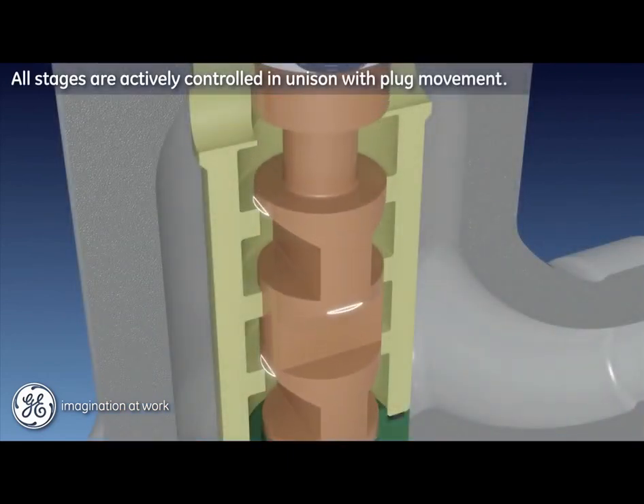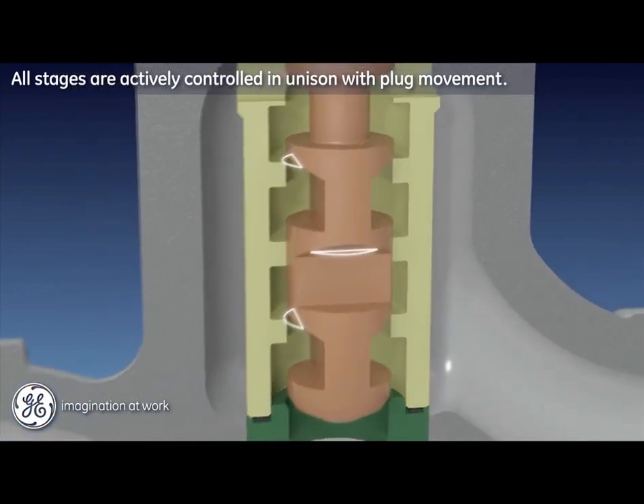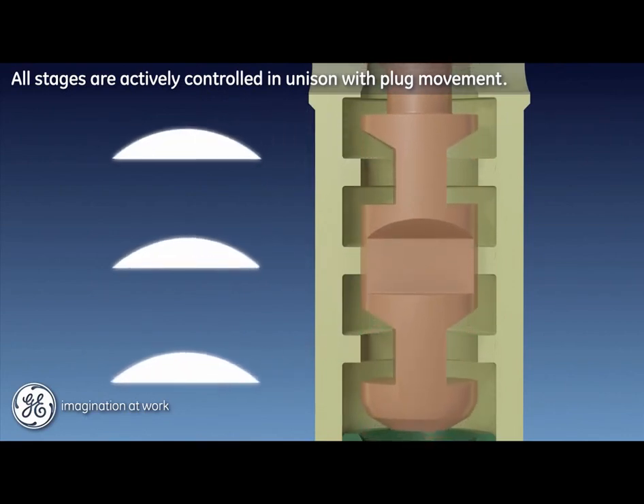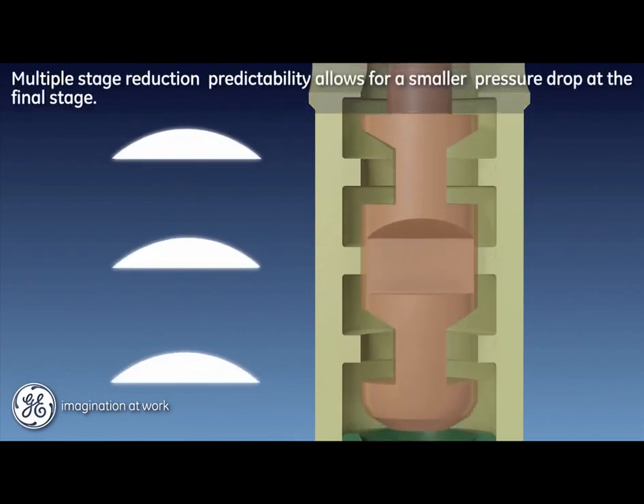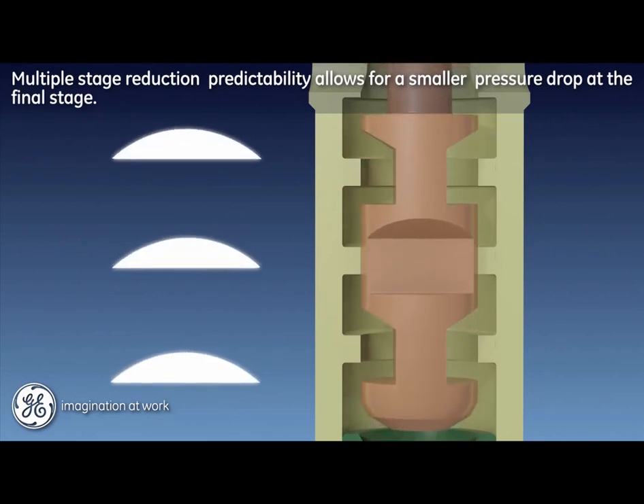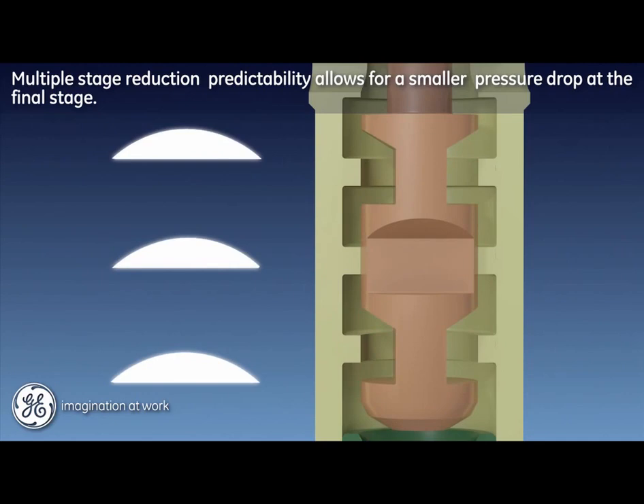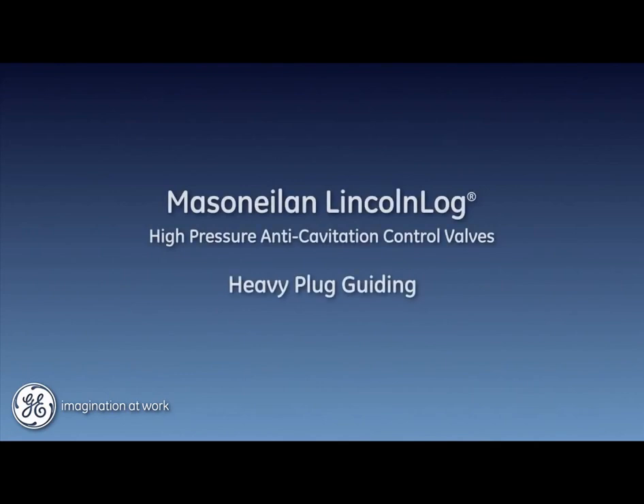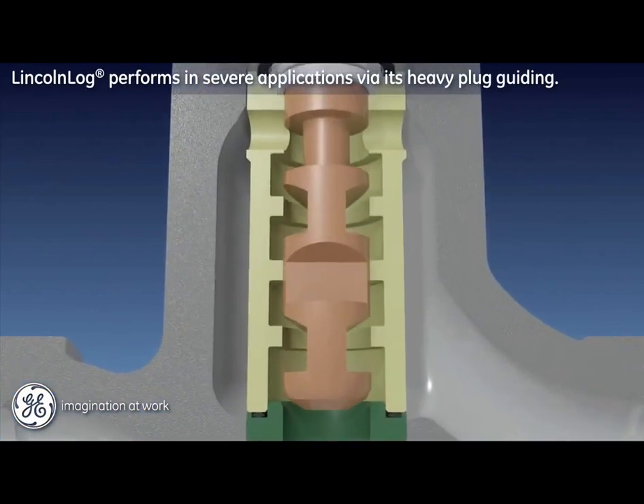A notable feature of the LincolnLog trim design is that all stages are actively controlled in unison with plug movement. The proportional resistance created by this unison staging provides the necessary predictable fluid energy management for high pressure drop applications. This predictable reduction at each stage concludes its mission with a smaller, managed pressure drop at the final stage, where cavitation risk is greatest due to the adjacent P2 pressure.